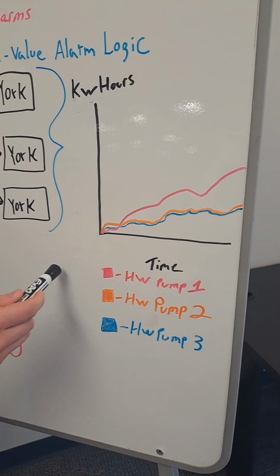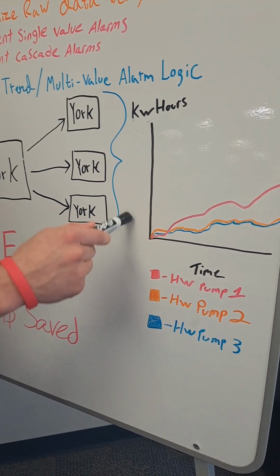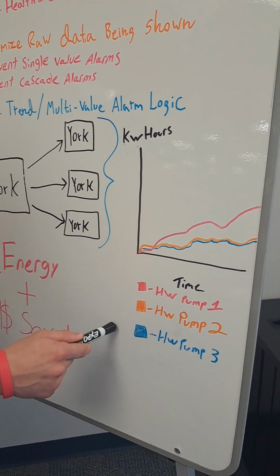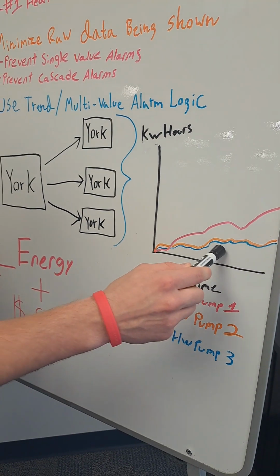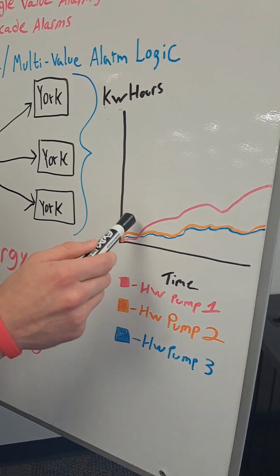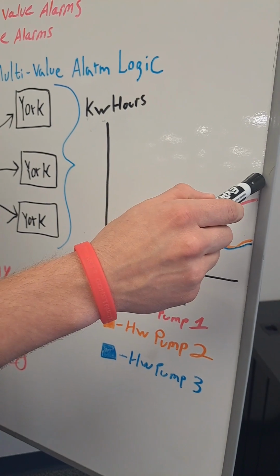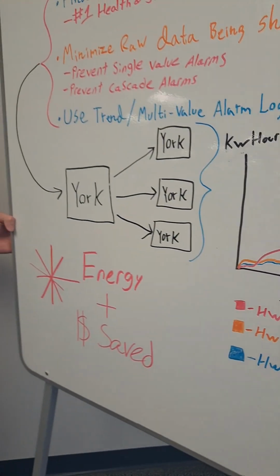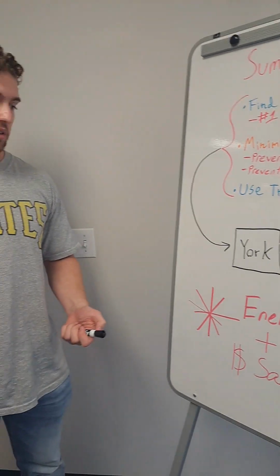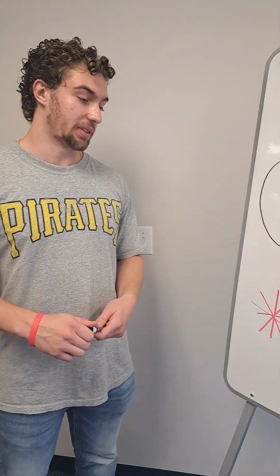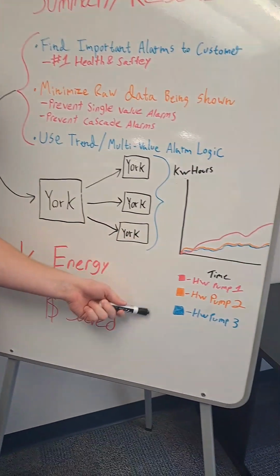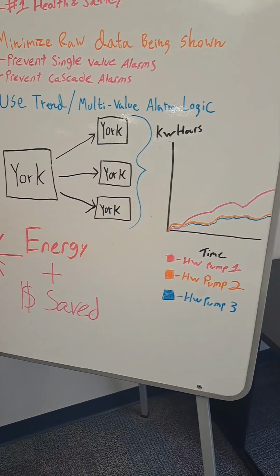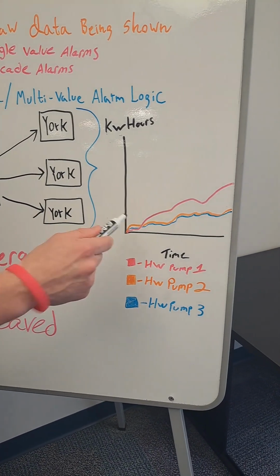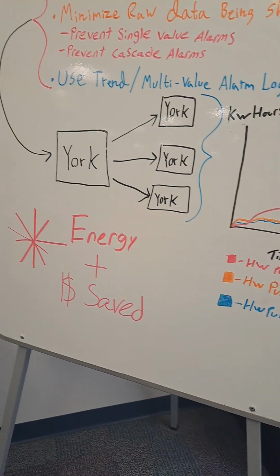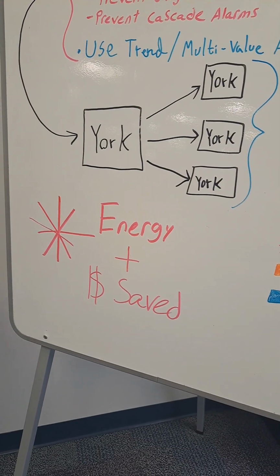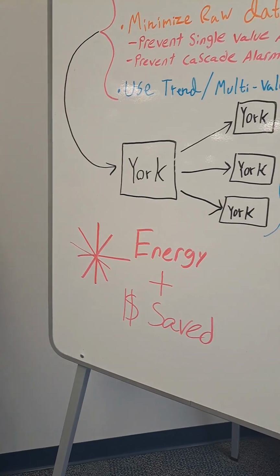As you can see, hot water pump 1 is using a lot more energy than these other 2 pumps, 2 and 3. They're pretty close together, steady going, but pump 1 over time keeps continuously increasing. So without a trend line, a customer might notice this on their electric bill, and it will take time to figure out what pump is actually causing the issue. With the trend line, we can clearly see that pump 1 is the issue, so we can quickly resolve the problem and save time and money and energy, which is the main point of a BMS system.